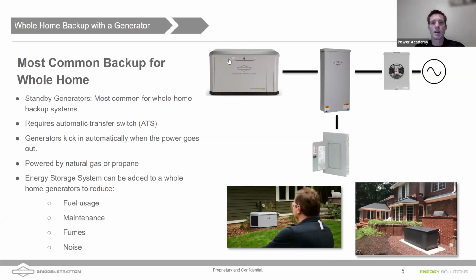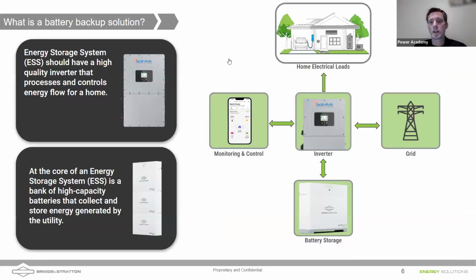It's a cheap way to store a lot of energy, but you still have to pay for that fuel. And I would argue that it's not necessarily that cheap. Some of these generators use 2 to 3 gallons of propane when they're running, and when propane's $3 a gallon, it can add up. So using the energy storage systems, maybe in combination with the generator, can save fuel, save noise as well. Yep. Noise, fumes, fuel. There are lots of reasons why customers are choosing to move to batteries, and I'm not saying that the generators don't still have their place.